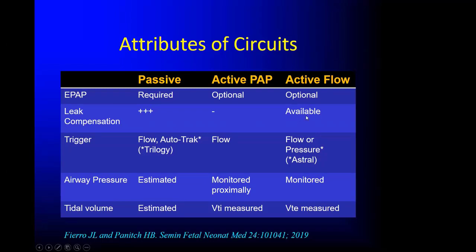Depending on the machine, you can use different triggers to start the breath. So most of these machines use a flow trigger, but the Trilogy has certain proprietary algorithms that are called Auto-Trak or Auto-Trak sensitive that are only usable with a passive circuit. As I mentioned, you can use flow with the active PAP circuit, and with the Astral you could use either flow or pressure, should you choose to. Airway pressure is estimated with the passive circuit, as is tidal volume. Whereas, as I mentioned, there's a proximal pressure monitoring tube in the active PAP circuit, and you measure the inspiratory tidal volume.